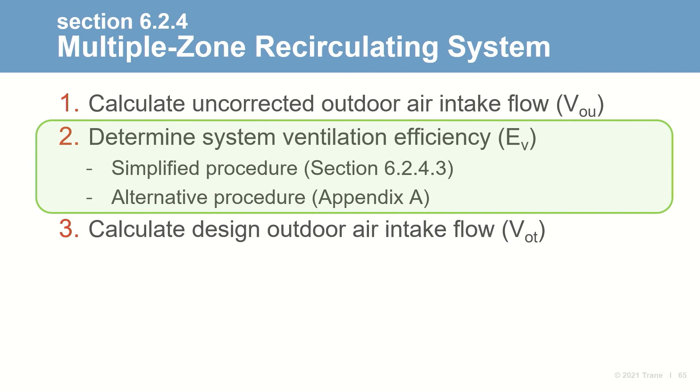This uncorrected intake flow would be required if the system were 100% efficient at delivering outdoor air from the intake to every breathing zone. Since that's not the case, the next step is to determine the system ventilation efficiency. Standard 62 includes two methods: a new simplified procedure, or the alternative procedure in Appendix A. Beginning with the 2019 version, the simplified procedure replaced the previous lookup table. The alternative approach might result in a higher efficiency and lower intake flow in some cases, so it may be worth the effort.